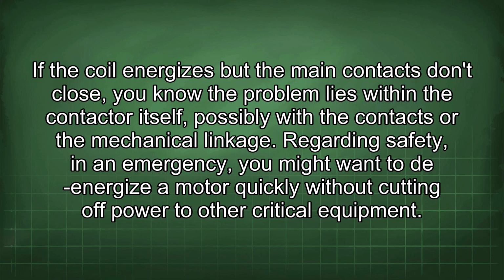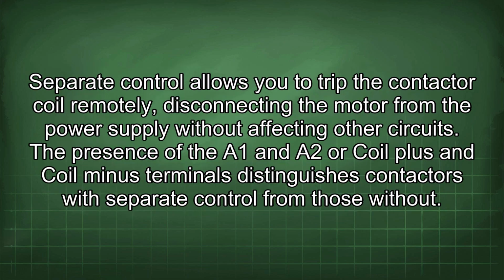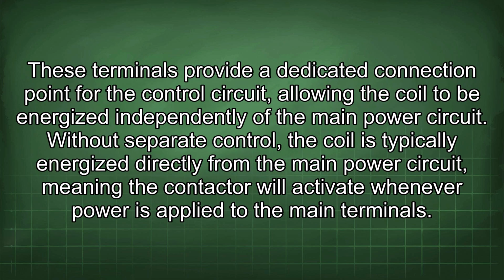Regarding safety, in an emergency, you might want to disconnect the motor quickly without cutting off power to other critical equipment. Separate control allows you to trip the contactor coil remotely, disconnecting the motor from the power supply without affecting other circuits. The presence of the A1 and A2 or coil plus and coil minus terminals distinguishes contactors with separate control from those without. These terminals provide a dedicated connection point for the control circuit, allowing the coil to be energized independently of the main power circuit.